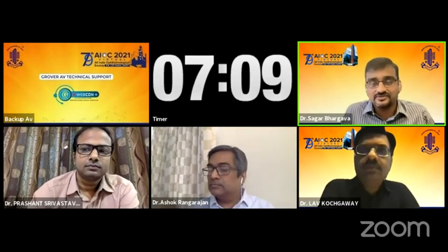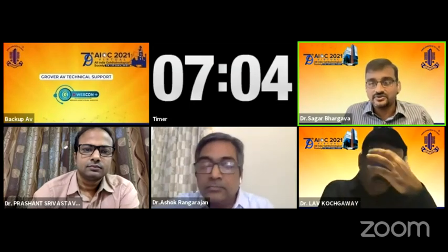One thing I have experienced with Verion is that it has a lot of noise somehow. If 8 out of 10 readings are good, for the 2 readings that it gives, you really have to crack your head as to why this has come and why it has so much variation. So there is the other machine. Yes. The technical person who's taking the measurement also has to be quite understanding about the whole thing, because that makes a huge difference. There is a learning curve in acquisition of the image.